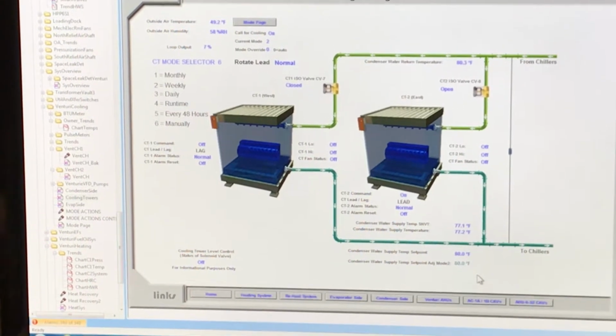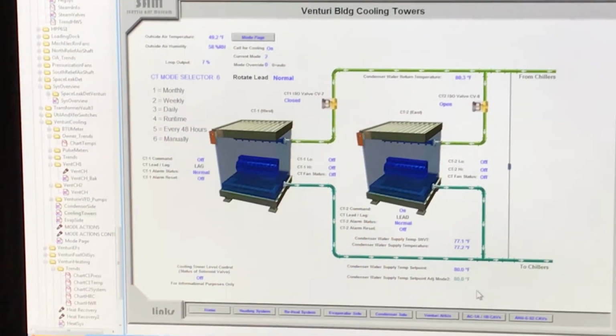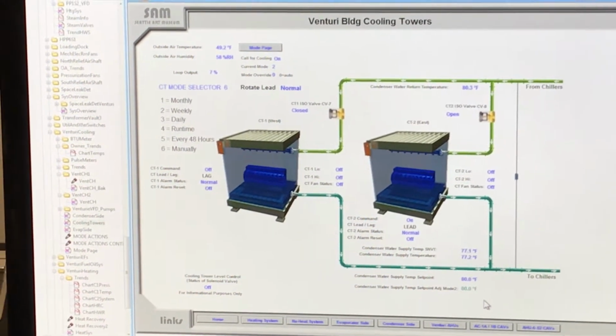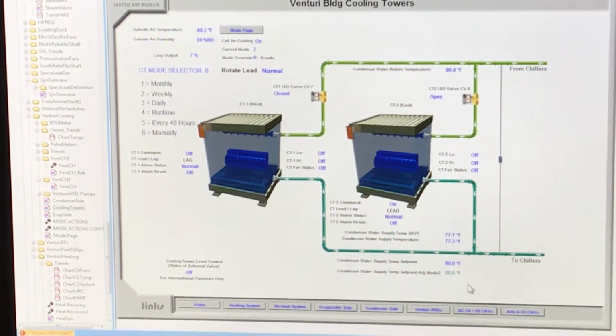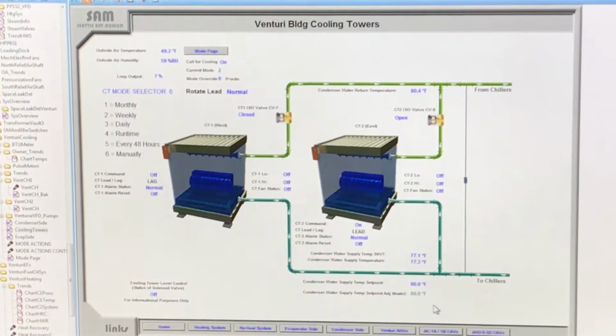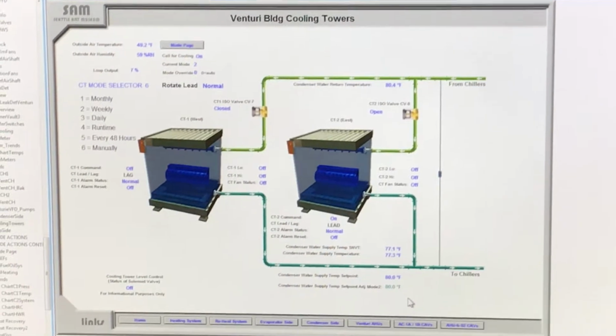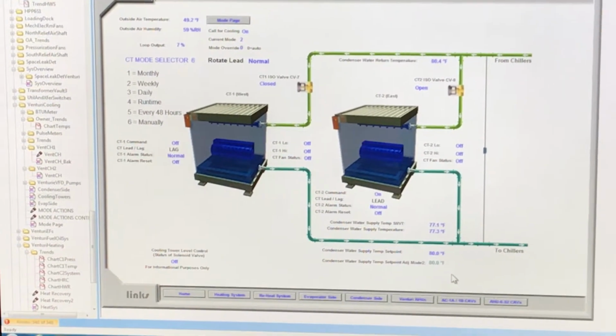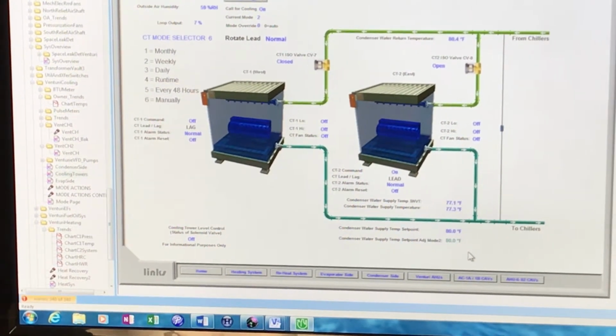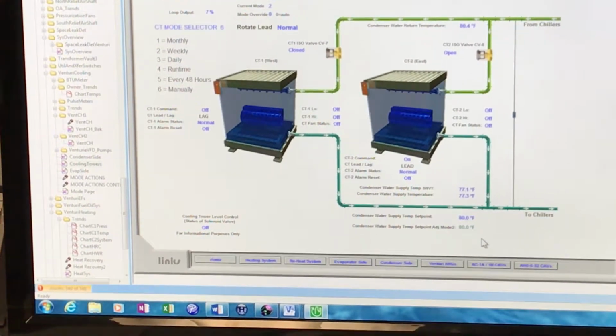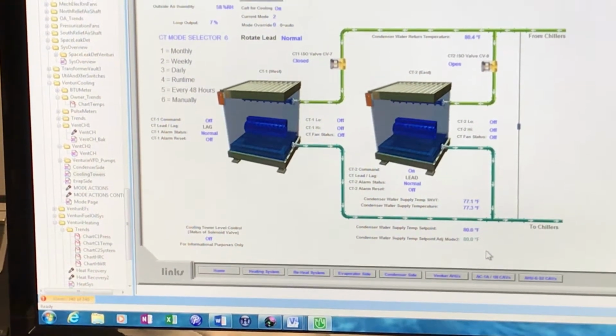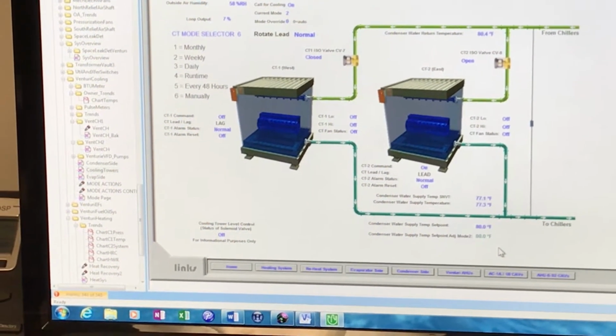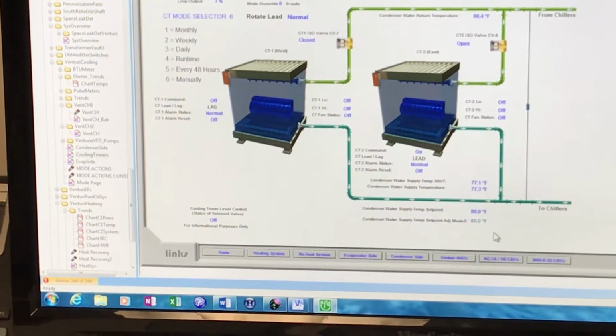And so usually you also do not want too low a temperature, because you're basically wasting your energy when you're running in a heat recovery mode where you don't need 60-degree water. That's right. And so I think that's why in mode 2, the program sets it to about 80 degrees, and then in the other mode, I think it's reset based on outside.